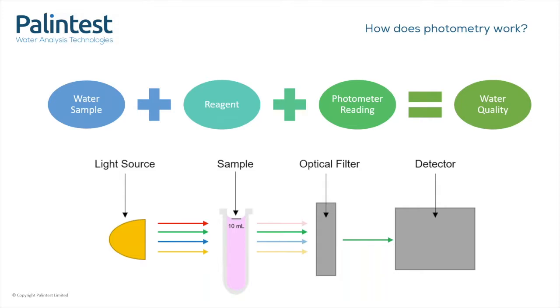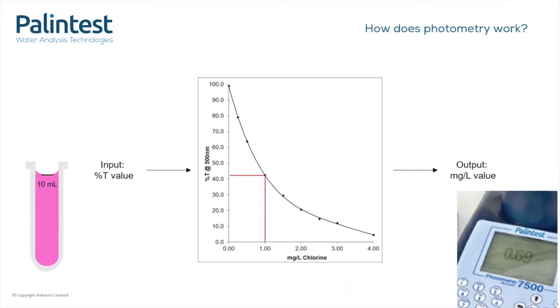The instrument measures the percent T through the sample in comparison to the blank. The blank is the sample without any reagents in it. Light passing through a glass tube of water will behave very differently to light passing through air, and that's why it's important to use a reagent-free sample as a blank. So, once we have the percent T, we need to convert it into something meaningful, something we want to use.